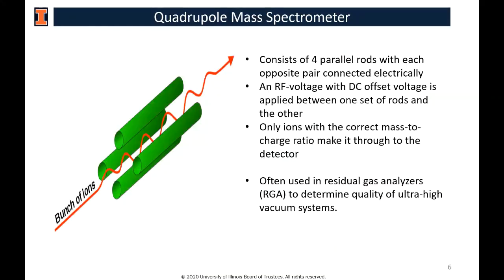There are three major classes of mass spectrometers used for SIMS analysis. The quadrupole mass spectrometer consists of four parallel rods energized by RF and DC voltages to limit passage of ions to only those with the correct mass-to-charge ratio. Advantages include small size and low cost, but it has poor mass resolution of about 1 AMU, so it can't distinguish between CO and N2, which both occur at 28 atomic mass units. It's also not designed for imaging.